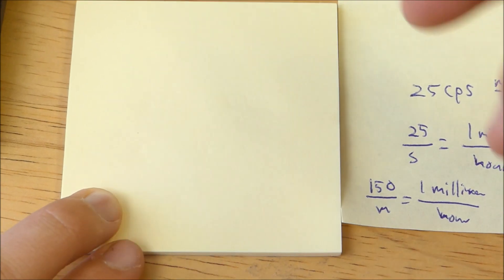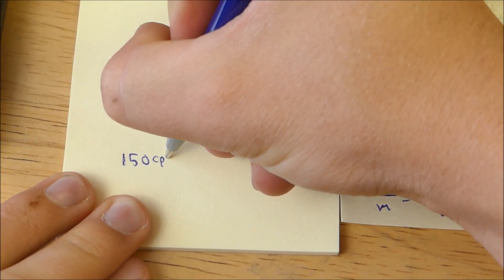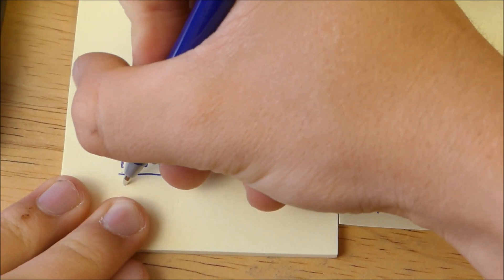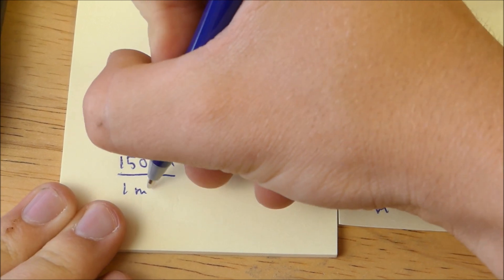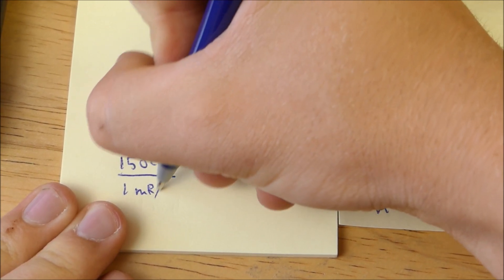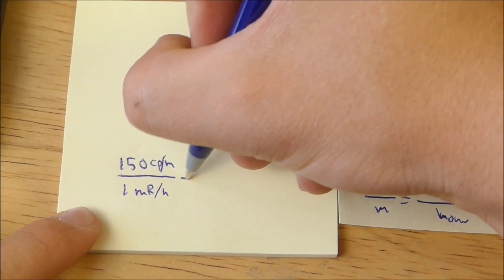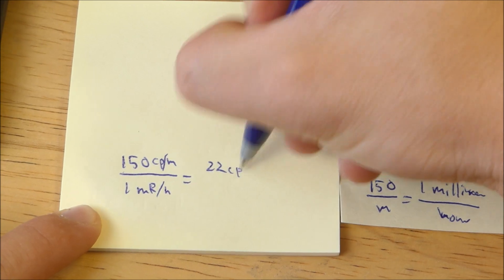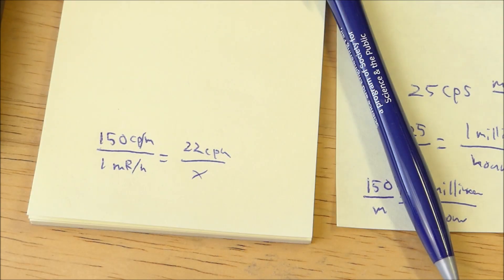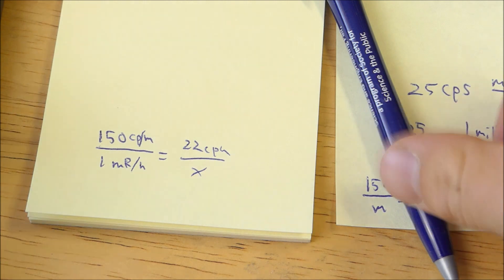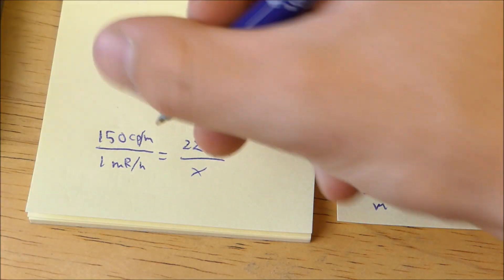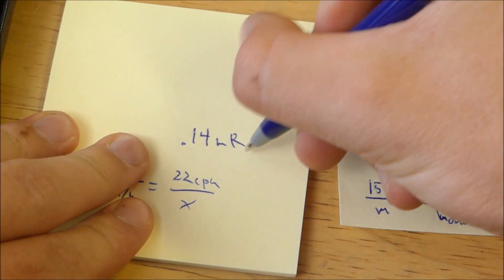So let's see. Alright, so here's how we're going to do this. We have 150 CPM is equal to 1 millirem per hour. And then what we can do is we can set that equal to 22 CPM equals x millirems per hour. That means the approximate background radiation of my room is equal to 0.14 millirems. So this is 0.14 millirems per hour.